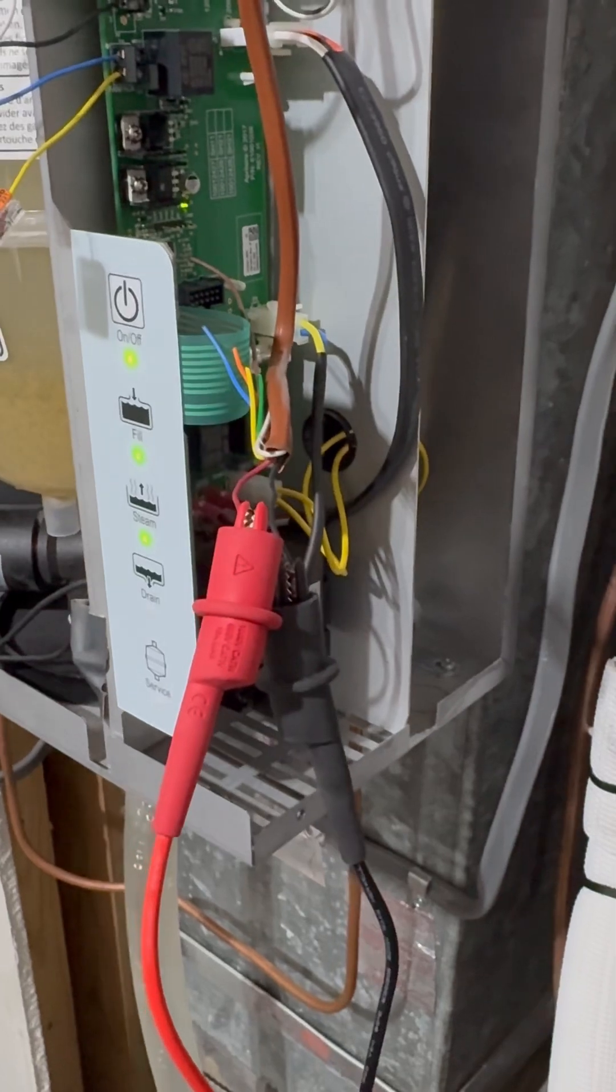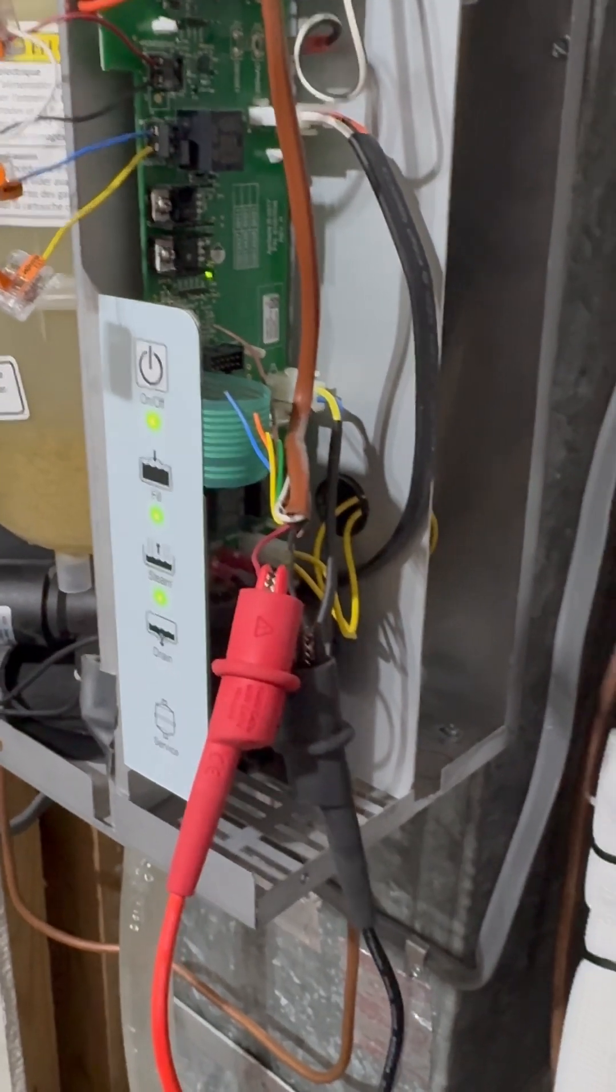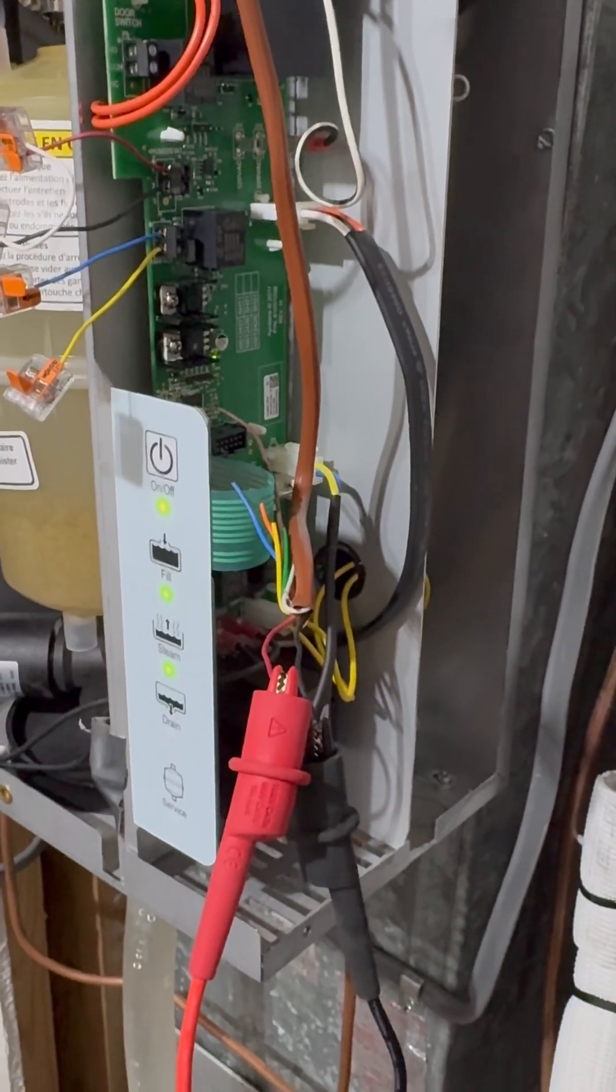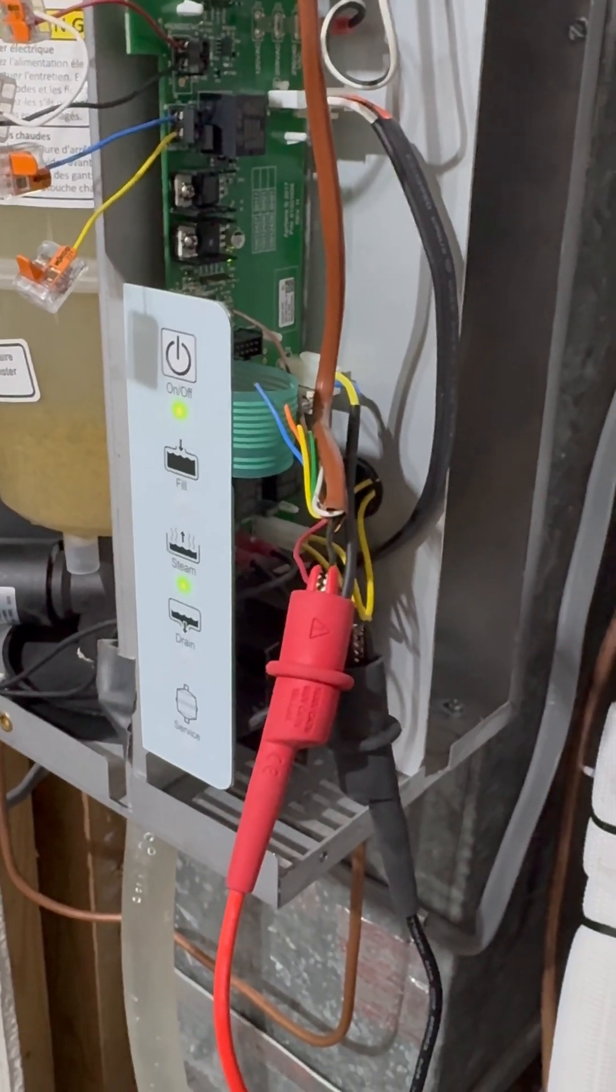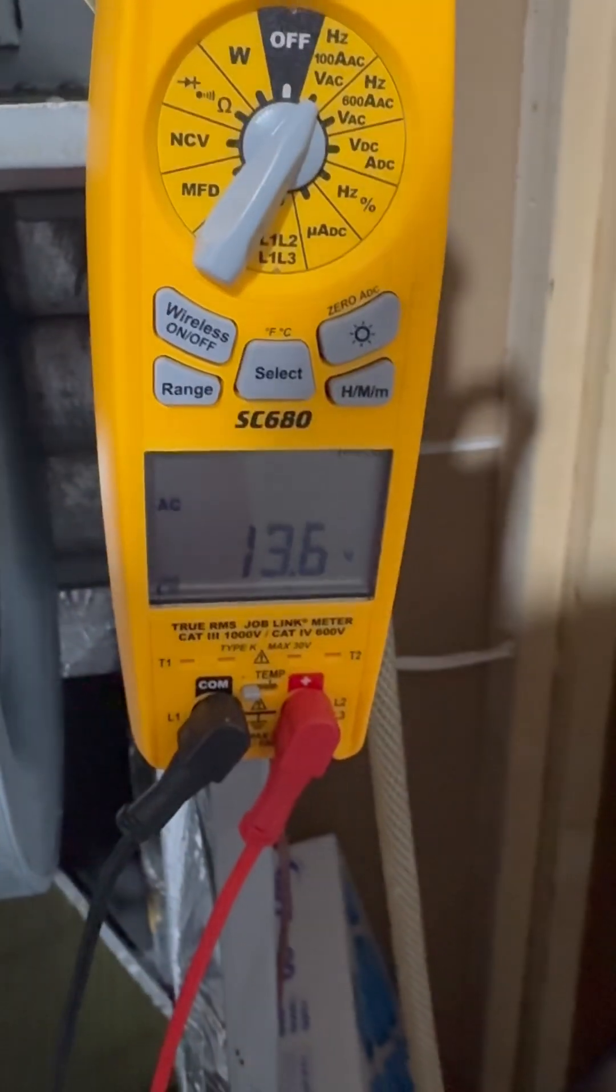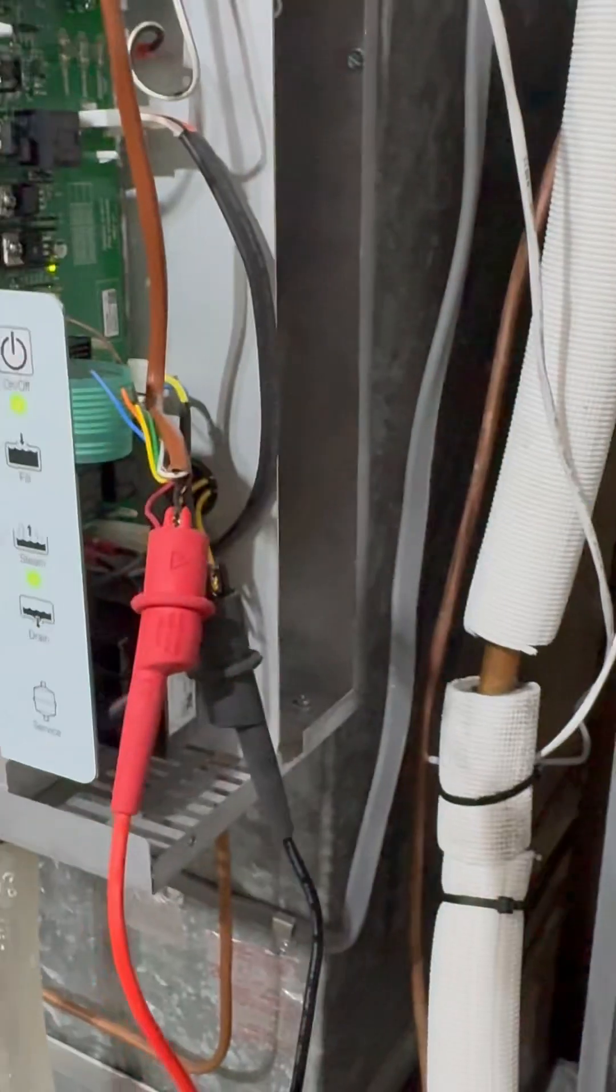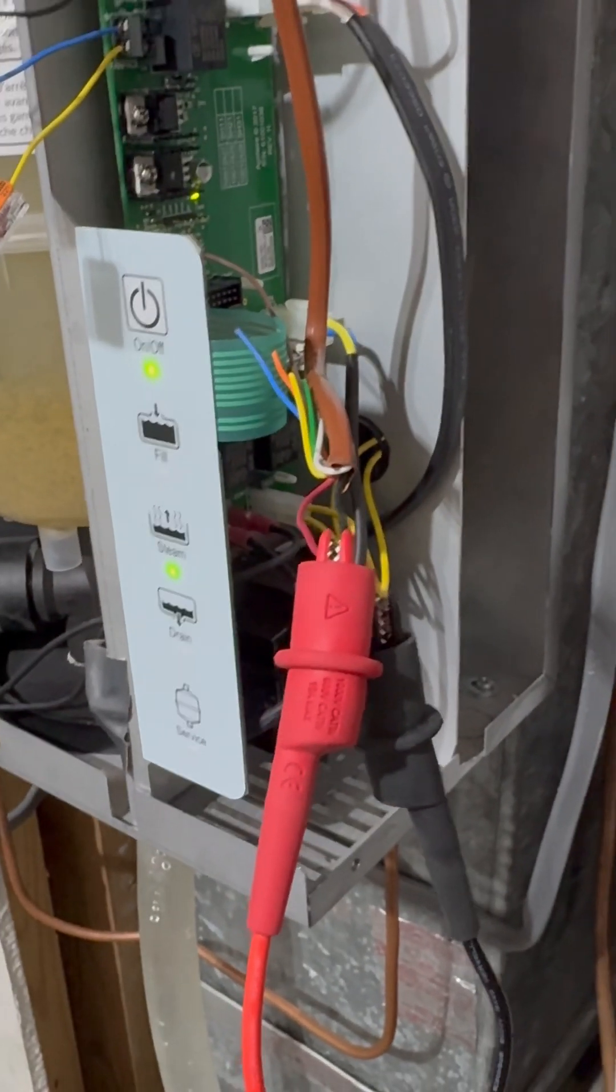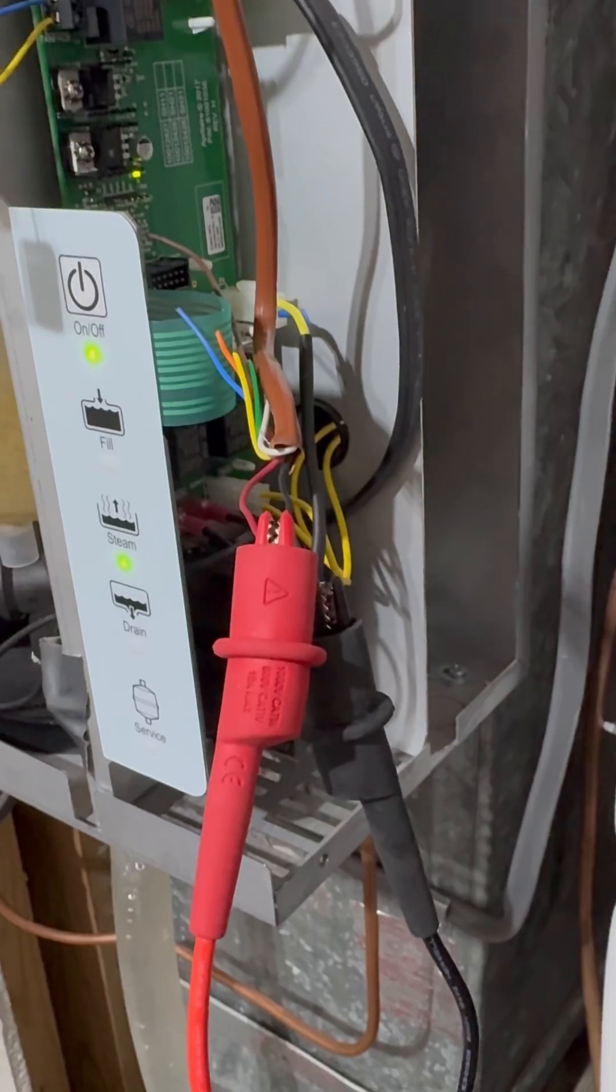So I'm going to show you how to go behind the scenes on the Ecobee to have it operate as a dry contact instead of a 24-volt signal, which in this case isn't even a 24-volt signal - it's 13.6, which is another question altogether. So stand by for more.